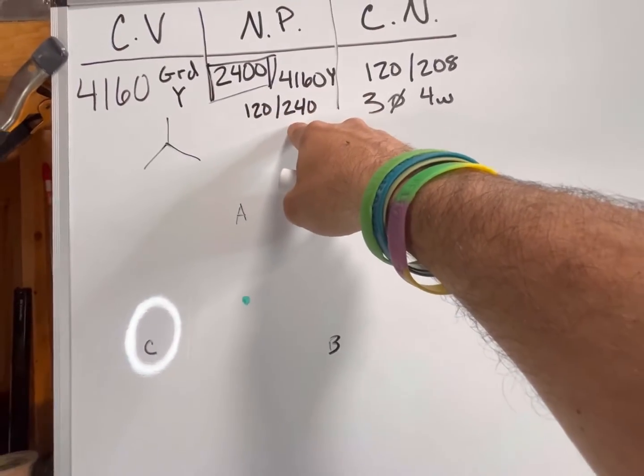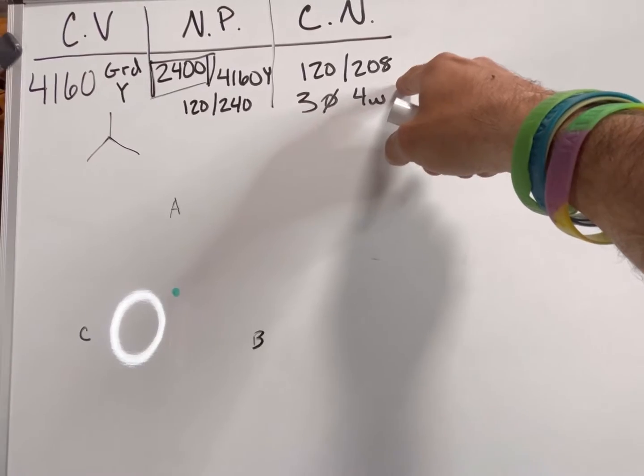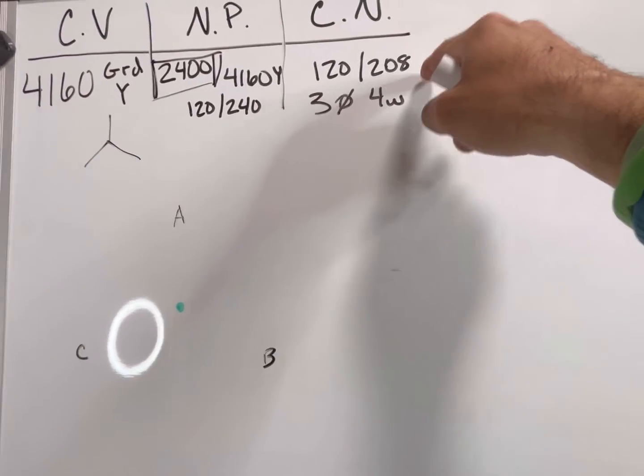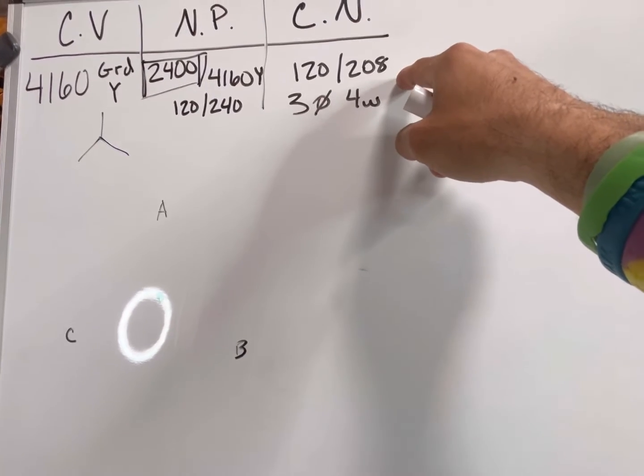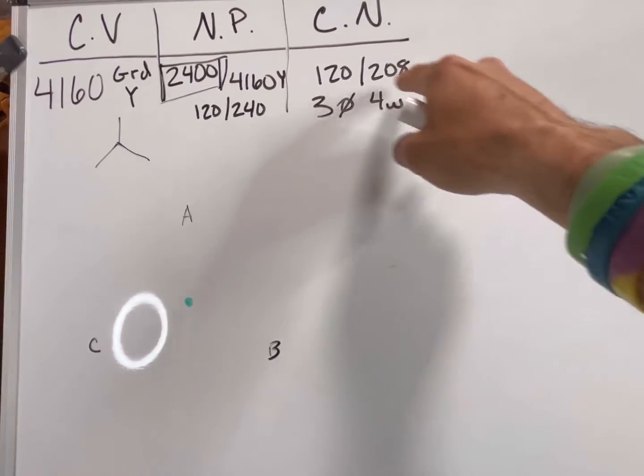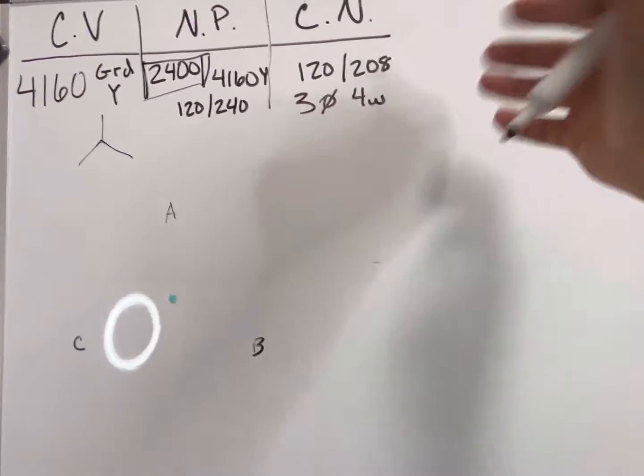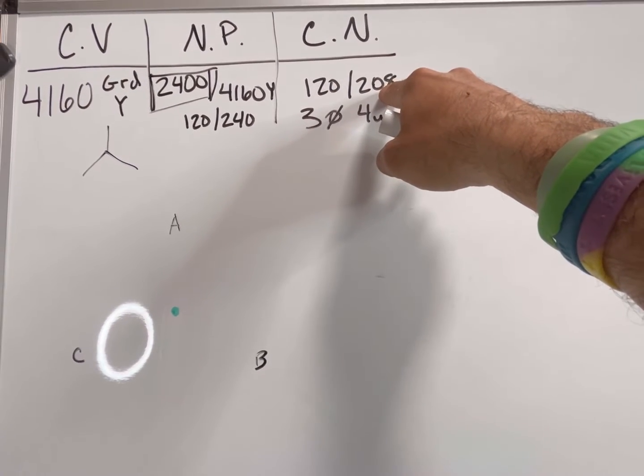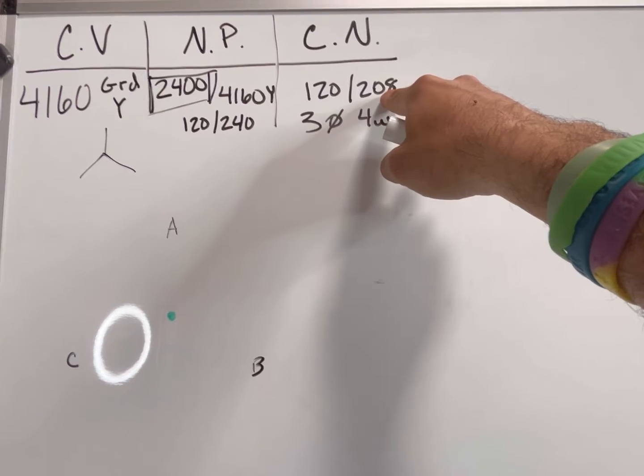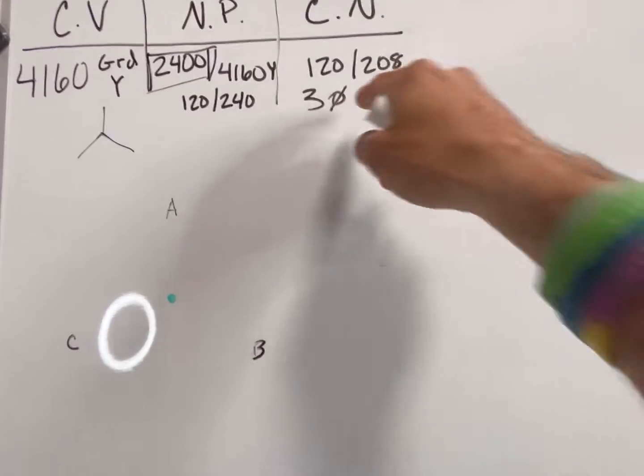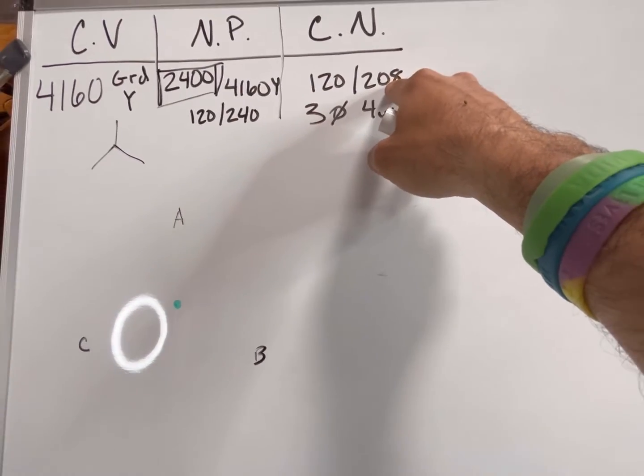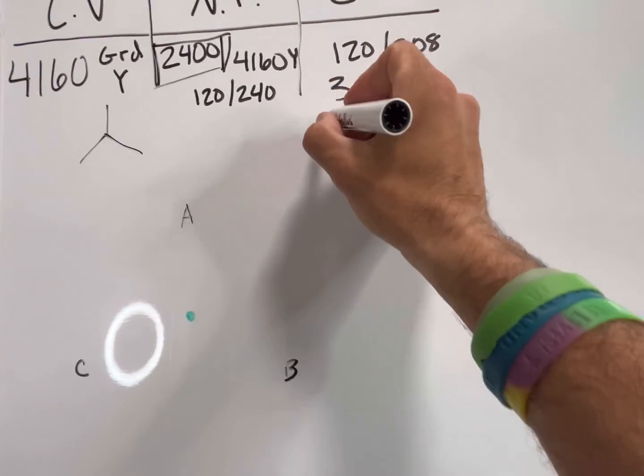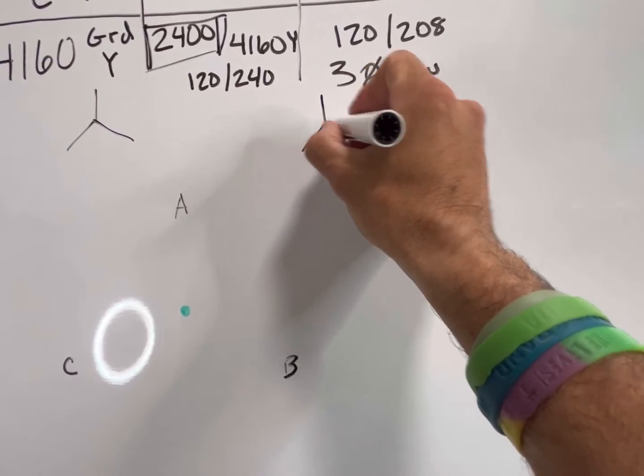I've got a 120/240 secondary and the customer needs 120/208. The customer's needs always determine the secondary hookup. So 120/208 — remember the rule: delta divides evenly. Does 120 divide evenly into 208? No. Therefore the secondary connection is going to be a Y.